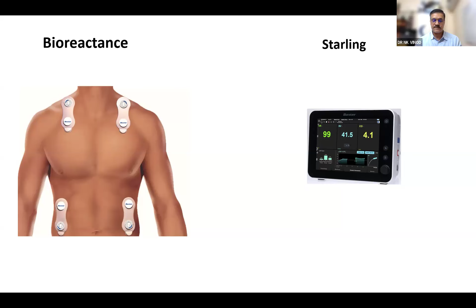In this machine, we have 4 non-invasive sensor pads which are applied to the thorax, which are creating a box around the heart. A small electrical current of 75 kilohertz alternating current is induced through the electrodes. Usually, the current is induced from the outer sensors, and the voltage signal is recorded between the inner pair of sensors. The flow of blood in the thorax induces a time delay or a phase shift in the signal, and this monitor uses this phase shift as the baseline for stroke volume measurements.